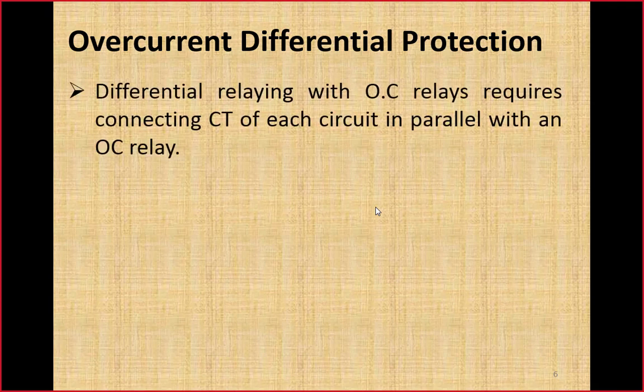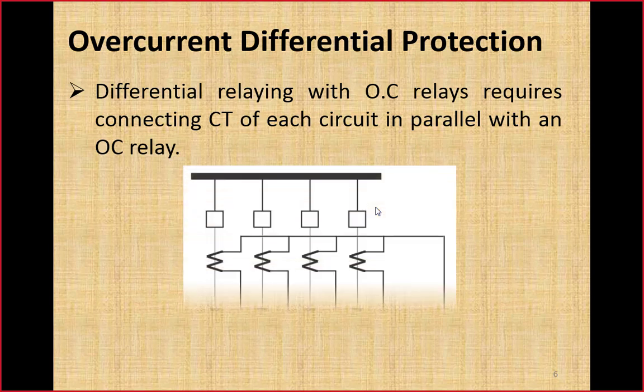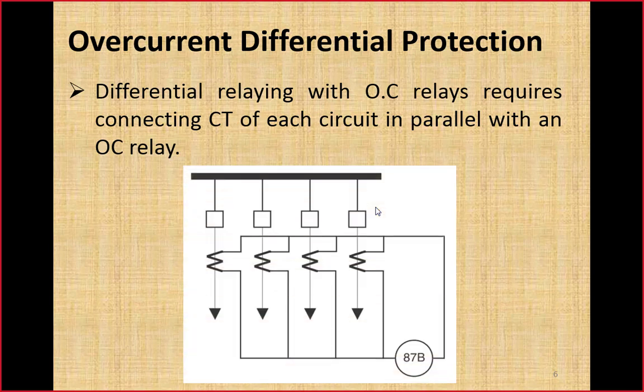Here we start discussion of application of overcurrent differential for bus bar protection. If we want to apply overcurrent differential for bus bar, first we will have to connect the CTs in parallel, and then the parallel combination of CTs will be applied across an overcurrent relay. This diagram will explain how the CTs will be connected together and then across the overcurrent relay. So this scheme will become overcurrent differential protection of the bus.